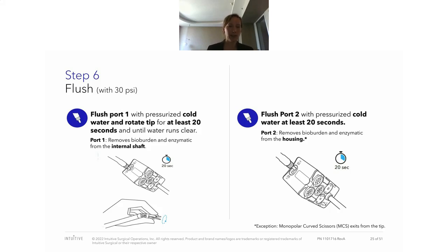And then after that, it's flush port 2. And as I mentioned, flush port 2 is the housing. And that is also flushed for 20 seconds. And in both cases, if the water does not run clear, the flushing needs to be prolonged until the water runs clear.